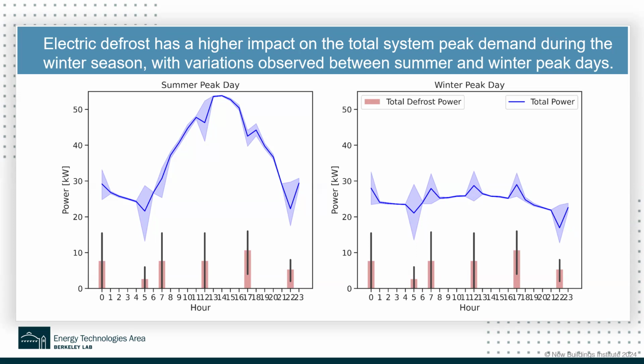But even though the defrost process can have an impact on the total refrigerant system's power demand, it may not have that much impact on a summer peak day because the compressor will dominate the overall system demand load. But for the winter time, the startup and the trickle-on of pressure over the defrost process has so much influence on the power demand, especially the load pattern. So this is what we thought about: how we can propose or develop an advanced defrost control process, as well as a new idea of using a liquid CO2 storage tank to take care of the peak demand. And let's jump on to the next slide.